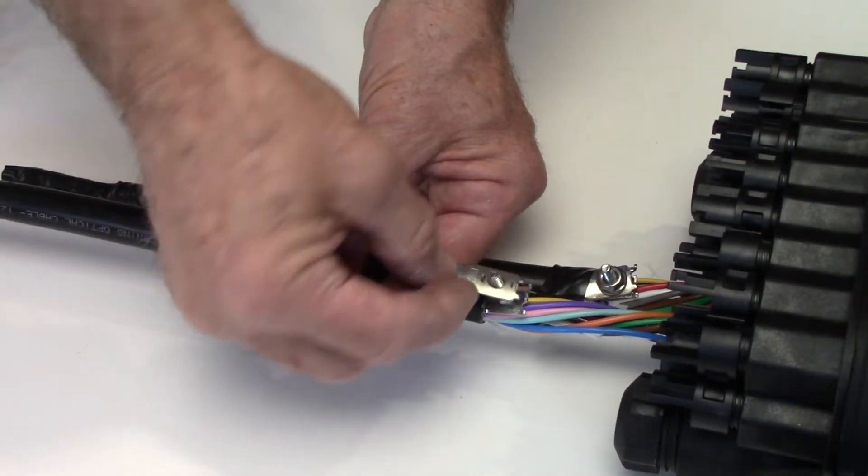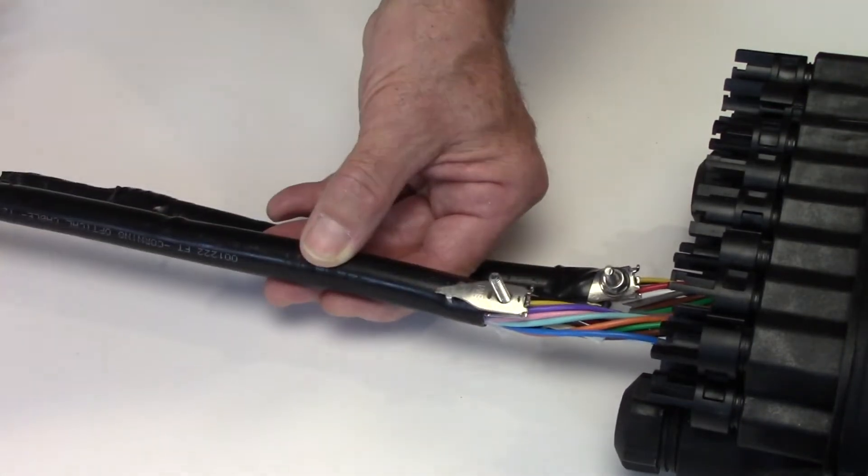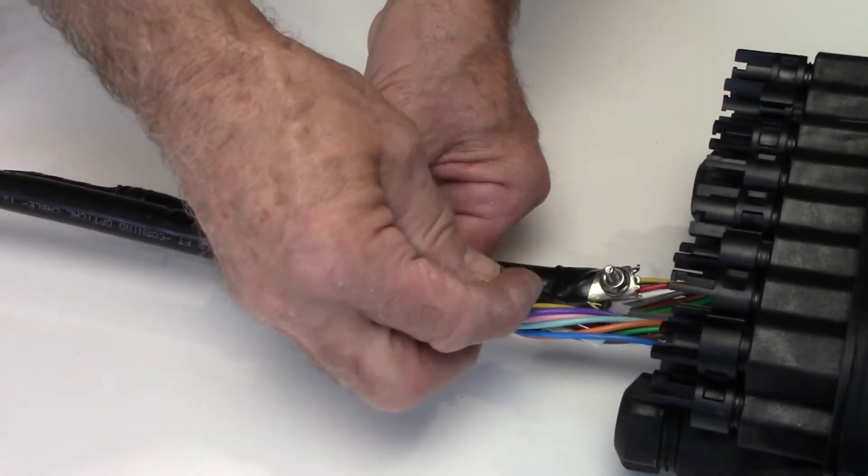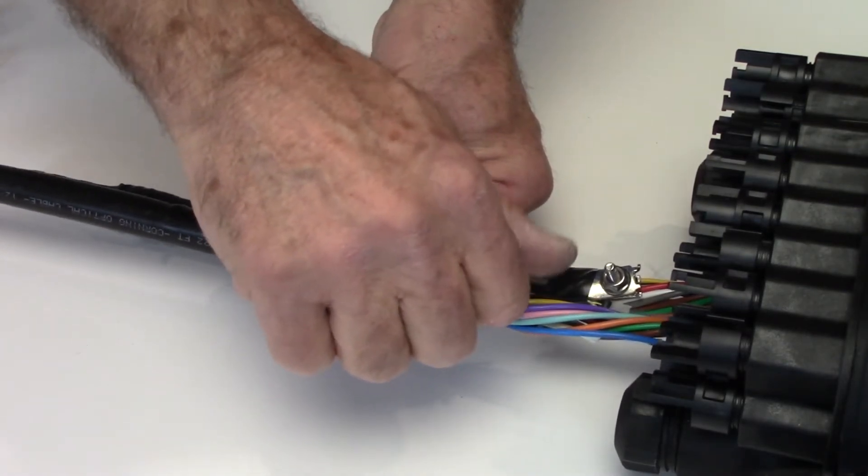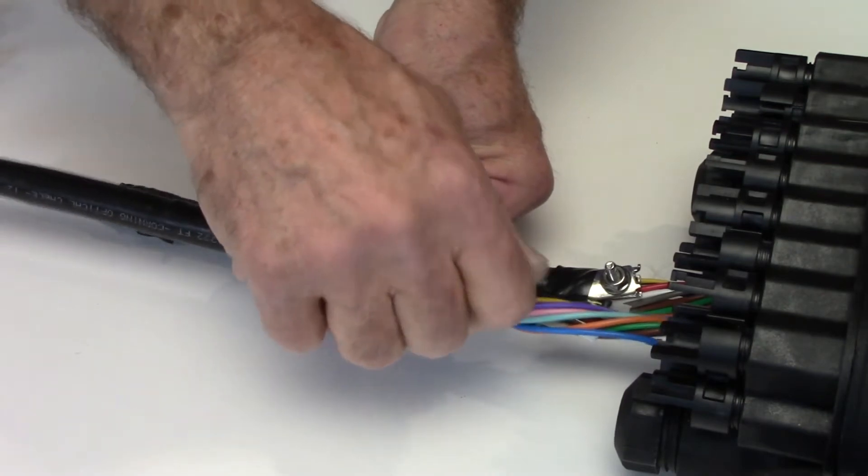If using armored cable and grounding is required, install approved bonding clamps on each side of the express cable loop. In this case, three M4460D bonding clamps are being used.